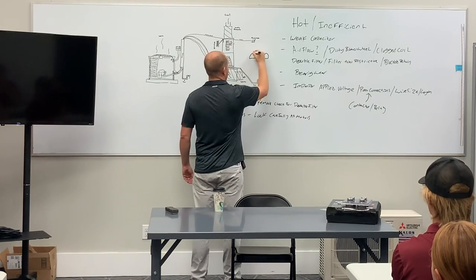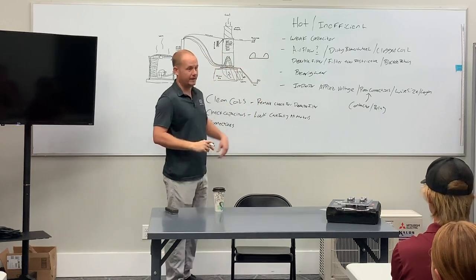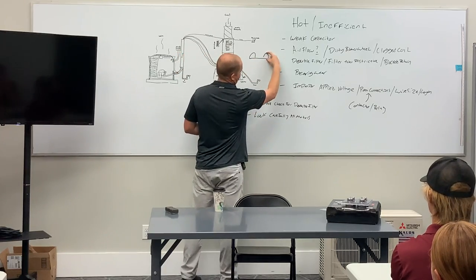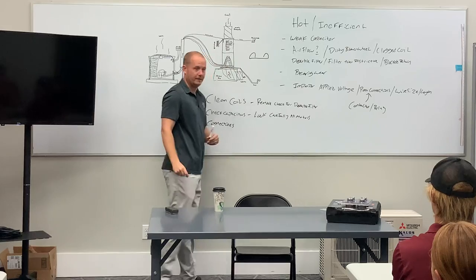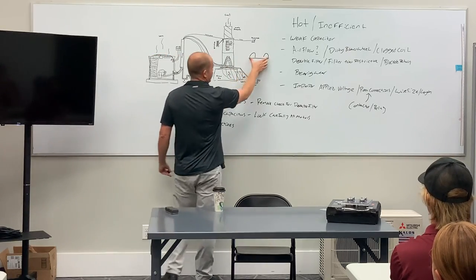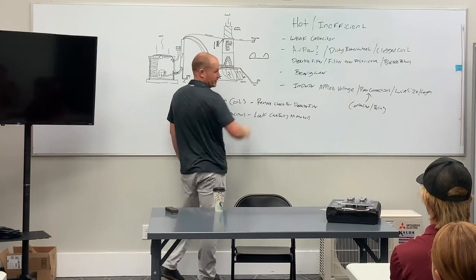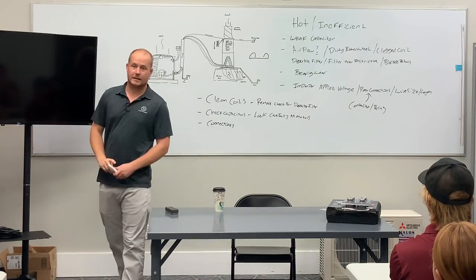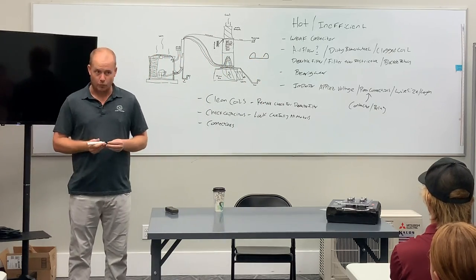if you look at the face of a spade, that's what it looks like, right? You're taking your needle nose and you're pinching here and here just a little bit in order to make it grab better. Because I've seen people pinching on the sides and that doesn't do anything. Pinch here, just a little bit. Make sense? That should be a regular thing you do.